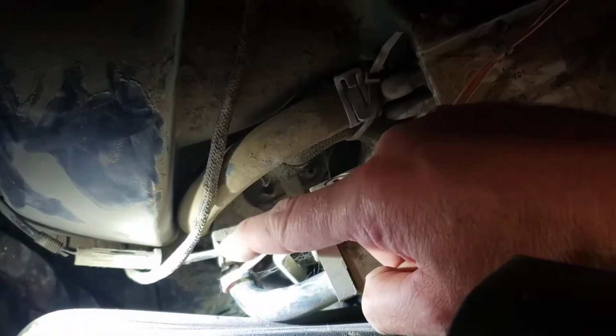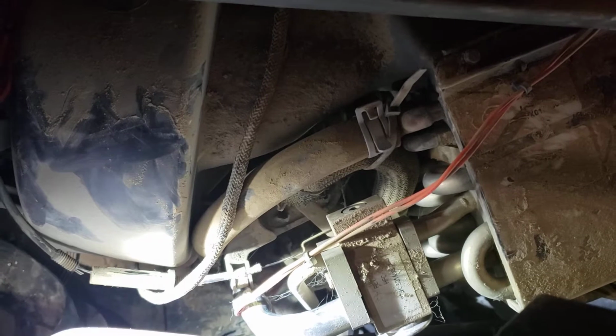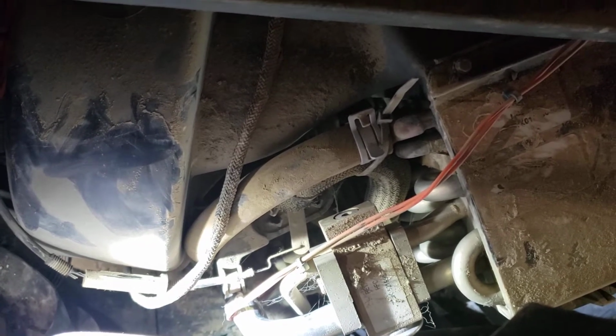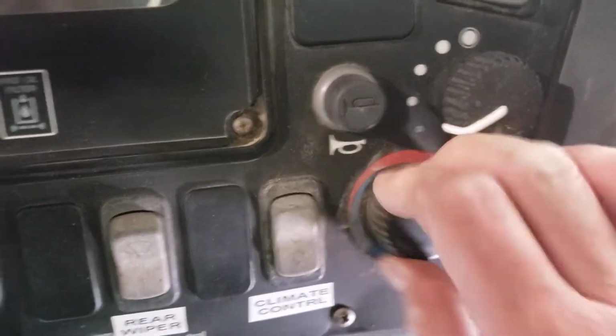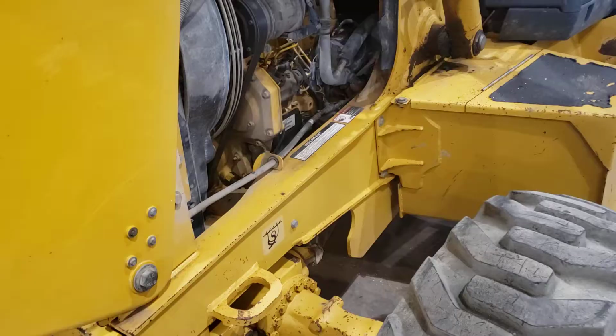So the water valve has a cable. The cable runs around this side. It's normally got the cover over it, but with the cover off, we can see the cable running around, and I can actually move that cable. See the cable moving down there, moving the water valve arm back and forth. So the way I'm moving that, full heat, full cool. So there's full cool, that's the water valve closed, and there's full heat, water valve open. So pretty simple control again, very similar to last week's machine.